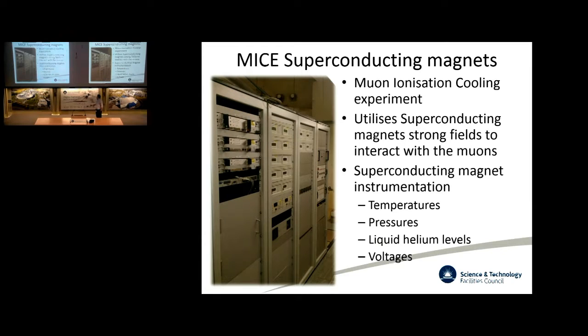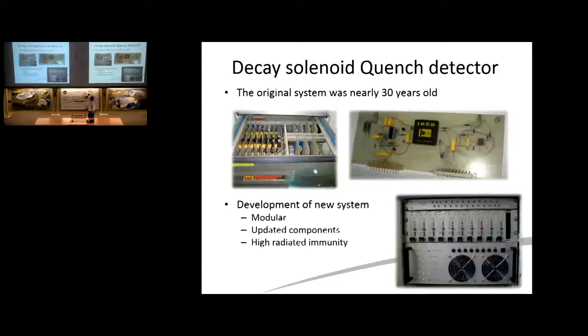And then we also want to keep an eye on the liquid helium levels to make sure that the magnet is in enough helium. So we use these AMI 135 units to keep an eye on the helium levels. And then I've put voltages there. Now this is the big one. Those of you who've got experience of superconducting magnets, you know that there's an expected number of training quenches, and obviously there's still the potential that it will quench when it's completed its training.